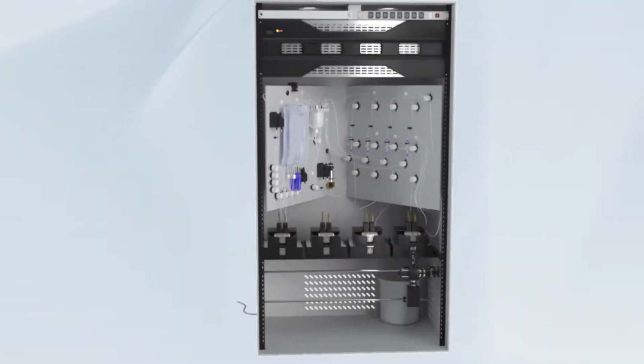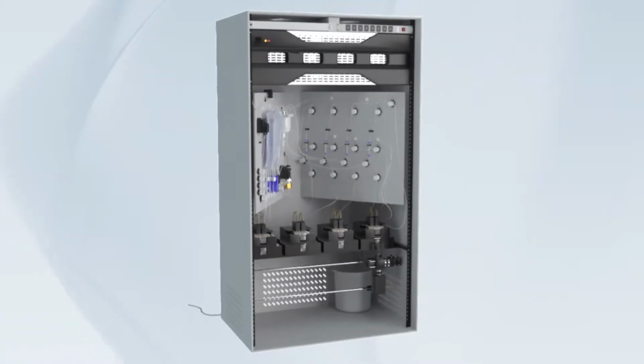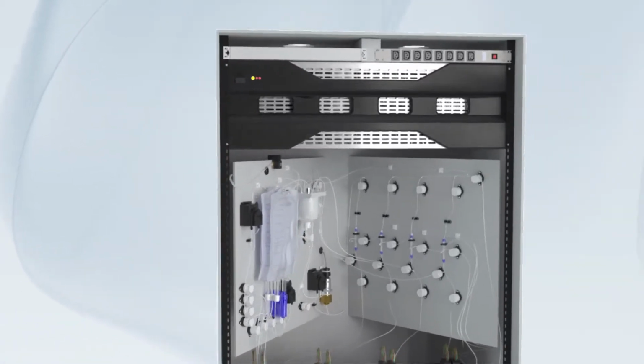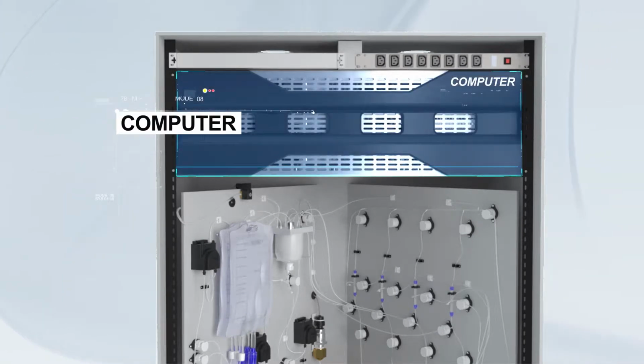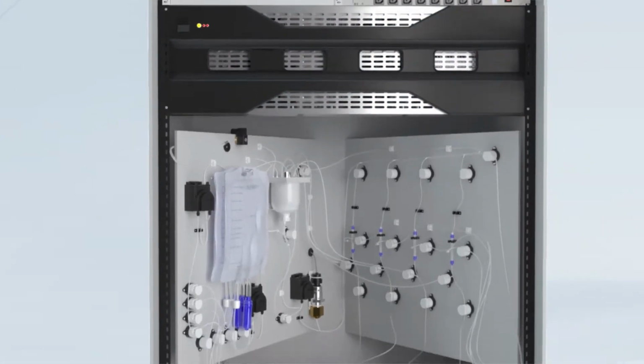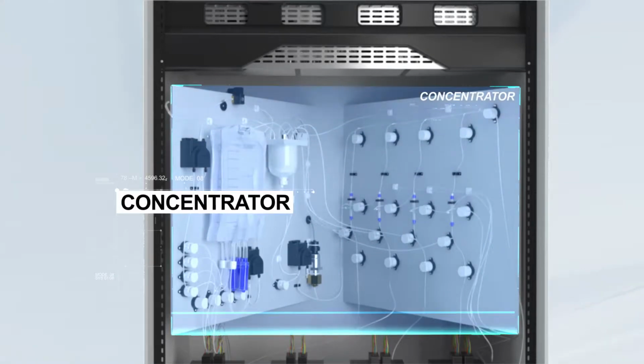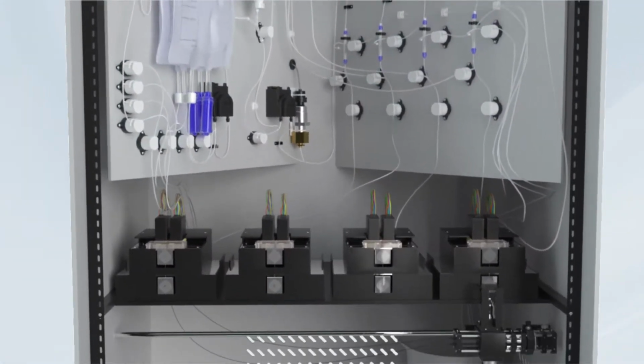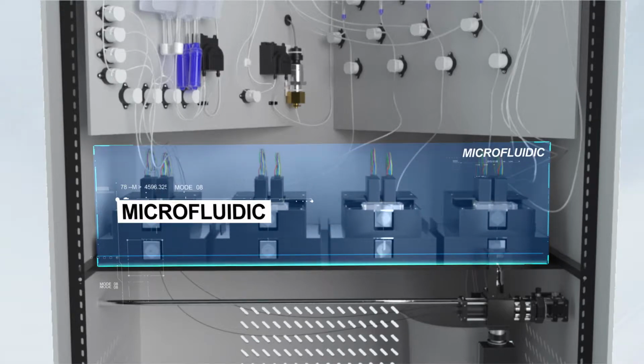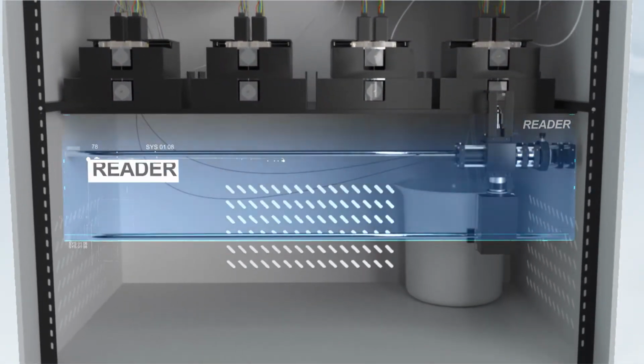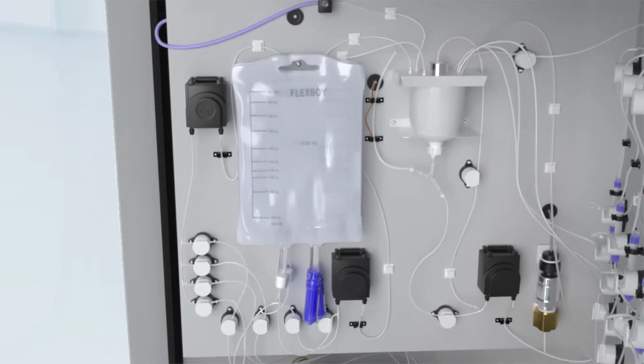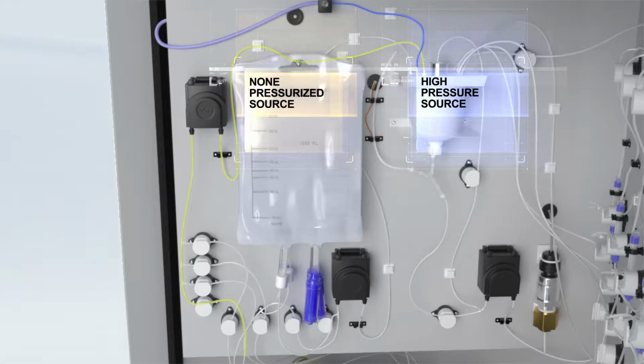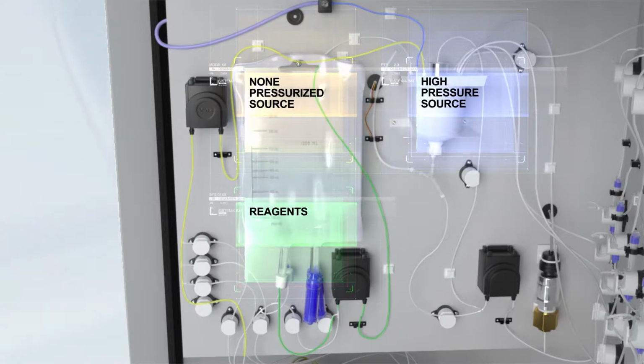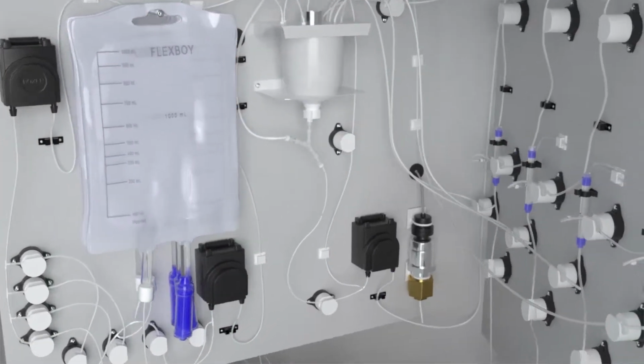The Cytowater system avoids sampling, transport, and manual concentration in the laboratory. The integration of 4 technologies in a single device enables a completely autonomous on-site microorganisms monitoring. The automated concentrator is capable of processing 4 water samples. According to the type of sample to be analyzed, water inlet is completed through either a pressure reduction valve or pumping from a non-pressurized vessel. The concentrator is capable of concentrating bacteria from the initial water sample into a final volume of 1 milliliter.